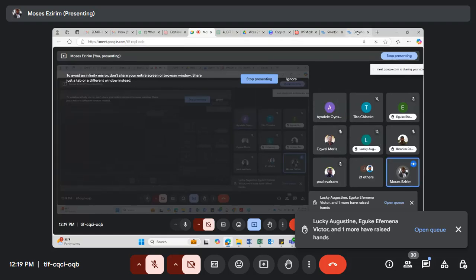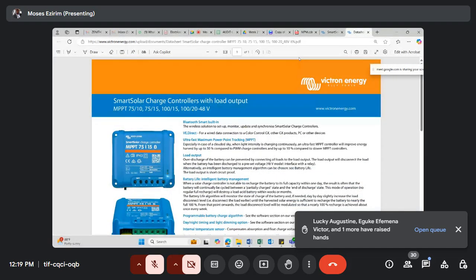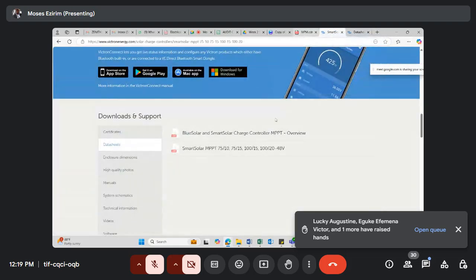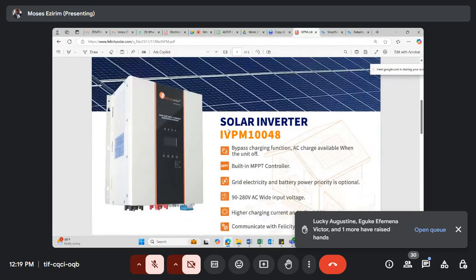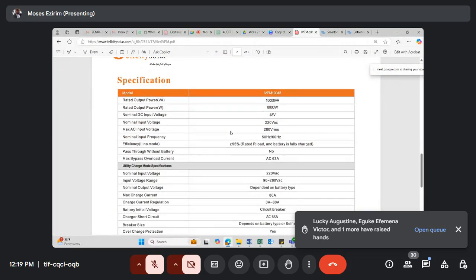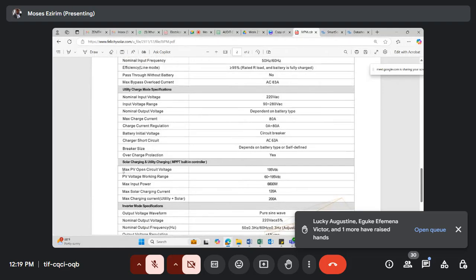Let me go to Victron. Now let me come to, if you check this, this is Felicity. Can you see my screen now? If you check the data sheet, it has solar, PV. It's talking about PV input maximum, you can check the data sheet. Looking at this, I know it's a hybrid, meaning it has inbuilt MPPT controller, you can even see MPPT built-in controller. So if you're checking a data sheet of an inverter and seeing among the data they talk about charge controller, maximum open circuit voltage, solar charging current and the rest, just know that it is a hybrid inverter.